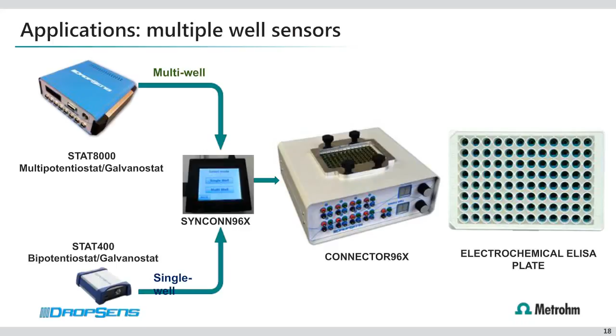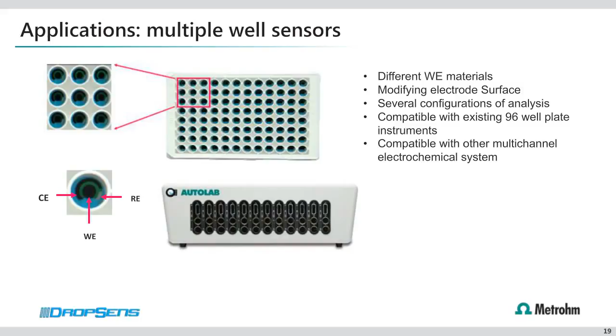Each well has at its bottom three electrode systems: a screen-printed working, reference, and counter electrode. Different materials can be used as working electrode: carbon, gold, platinum. As you already know, different modifications can be carried out on the electrode surface, with carbon and metal nanoparticles for example, in order to enhance the response. Therefore, in each column, we can run measurements applying the same technique for calibration or detection of the same analyte, and it's also possible to apply different techniques if we are analyzing different analytes in the same sample. The options are multiple, and this system is highly compatible not only with DropSens multi-channel systems, but also with any multi-channel potentiostat such as Metrohm Autolab.